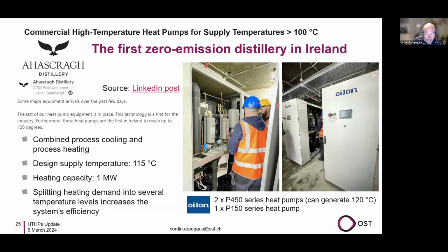Then, a realized example of a high temperature heat pump, which has been cited now several times, especially in LinkedIn posts and so on. It's in Ireland, the first zero emission distillery, called Ahascragh, I'm not sure if I spell it correctly. It's Irish. They have a heat pump that can generate up to 120 degrees; they actually need 115 degrees for the distillery process. One megawatt heating capacity. It's used for heating and cooling, so it makes use of the heat pump principle, really using both sides of the heat pump.